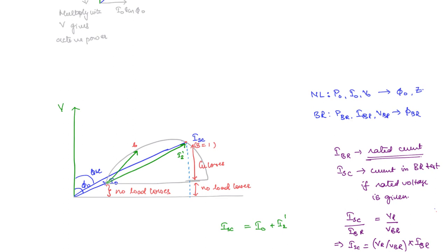Now further what we can do here, if you divide this line in the ratio of the rotor and stator resistances. Let us say this is a point here. We can take this point as A, this point as B and this point as C. Now we have another point D here. This is such that AD by DB is equal to R2 dash by R1, rotor resistance by stator resistance. We know the individual values. From the DC test we can find out R1, and from the blocked rotor test you can find out R2 dash.